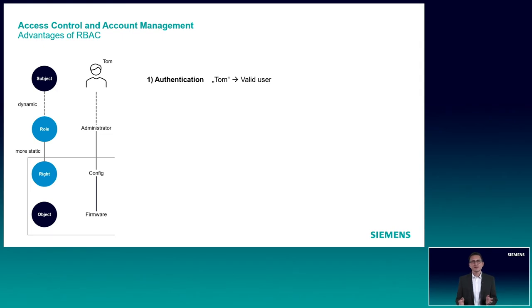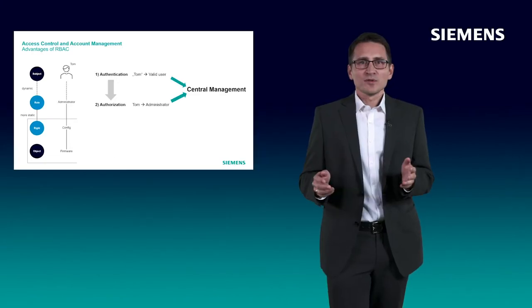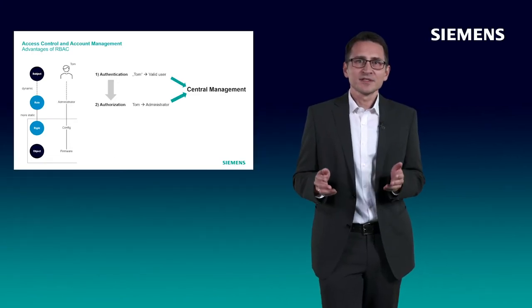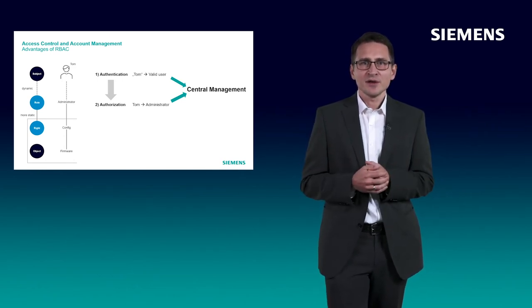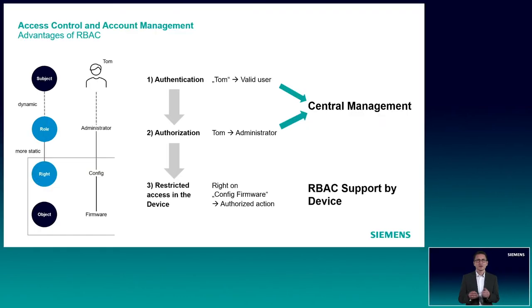The following methods are part of the role-based access control concept. The first step when Tom wants to connect to the device is the authentication. This means he provides the username and password. The second step is the authorization. This means that Tom is assigned the role administrator. Both authentication and authorization are centrally managed, for example in a central RADIUS server or Active Directory.